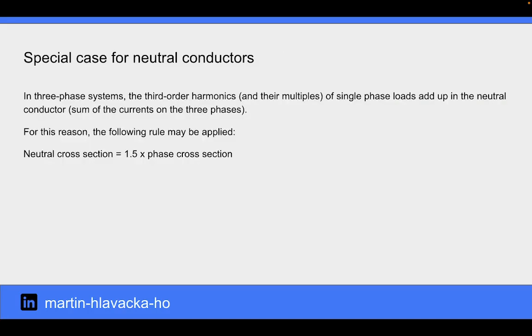In three-phase systems, the third-order harmonics and their multiples of single-phase loads add up in the neutral conductor. For this reason, the following rule may be applied. Neutral cross-section equal to 1.5 times phase cross-section area.